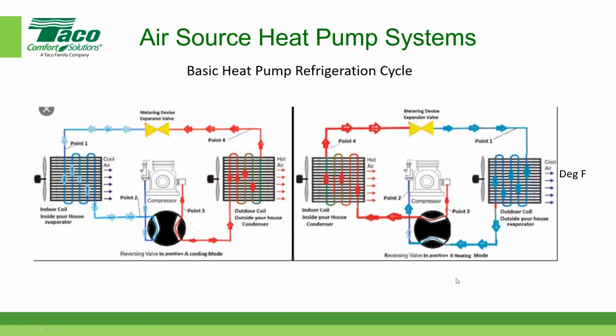So the defrost cycle changes depending on the manufacturer and the strategy that the manufacturer is using. But yes, all heat pumps that use the ambient air as a source for extracting heat do have to account for the outdoor unit generating ice, and they have to have some kind of de-icing or defrosting cycle in their system. Yep. Does that help?